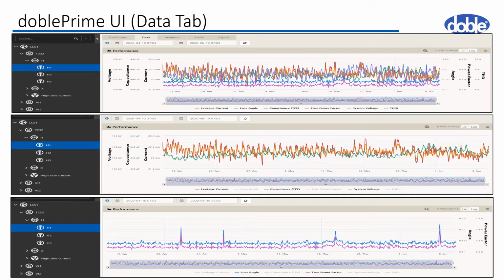For instance, in the center shot, it's widely known that the leakage current value is basically Ohm's law, which is I equals E divided by R, or in this case, I equals E divided by X sub C, and X sub C happens to contain the capacitance value. So it might be reasonable to view the primary voltage, the leakage current, and the bushing capacitance by turning off total harmonic distortion, THD, power factor and angle. You can see that the primary voltage and the bushing leakage current follow each other very closely. The capacitance follows a similar pattern.